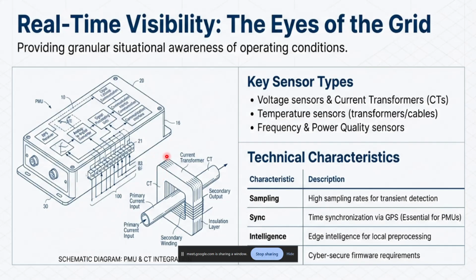So let's talk about the key components and their roles. We have common sensor types: voltage sensors, CTs (current transformers), and temperature sensors. These temperature sensors are mounted inside transformers or HT and LT panels. This is very critical, because most breakages happen due to increase in temperature. When we regulate this temperature and identify it below a certain threshold level, we can mitigate most accidents. So this is a critical sensor.